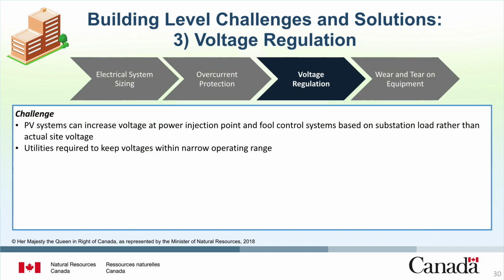Now we will discuss how voltage regulation can present challenges for a building integrating renewable energy systems and some solutions. Voltage regulation is often cited as the primary concern of utilities when considering interconnection of a renewable energy generator. PV systems can increase the voltage at the point where they inject power, and they can also fool control systems which are based on load on the substation rather than actual voltage at the site. Utilities are required to keep these voltages within a relatively narrow operating range. For example, a 120-volt service may vary from 114 to 126 volts, root mean squared.